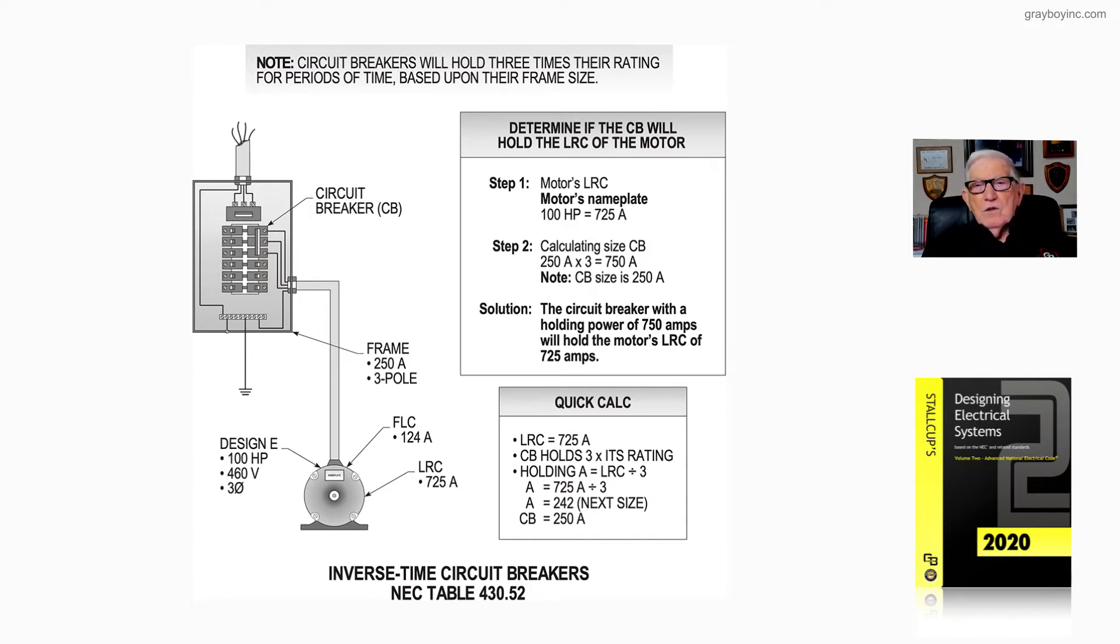We're going to determine what size circuit breaker would allow this motor to start based upon the LRC. Step one: 100 horsepower, 725 amp. We're saying that is the starting current value.